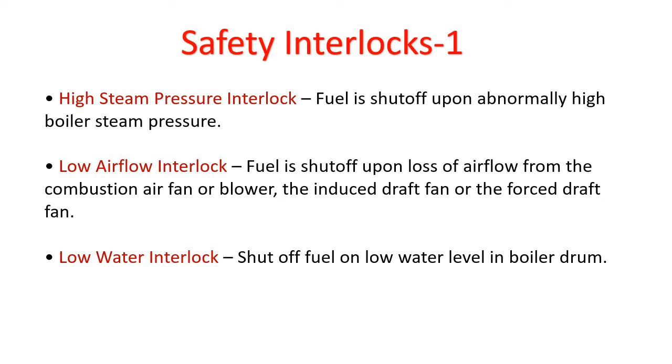Then there is the low water interlock. Again, if the water itself is less, then there is a chance of damage to the boiler tube, right? So shut off the fuel, and if you shut off the fuel, obviously your burning will stop, and that's how you can avoid the dry run of the boiler.